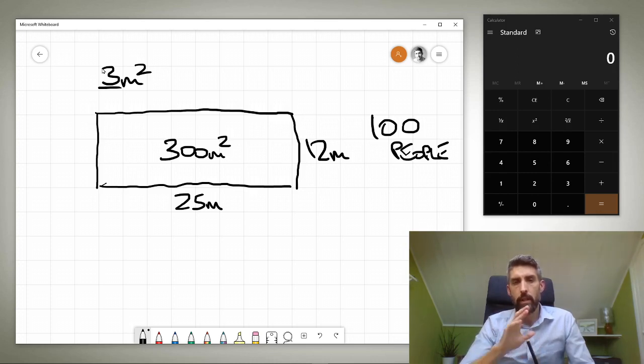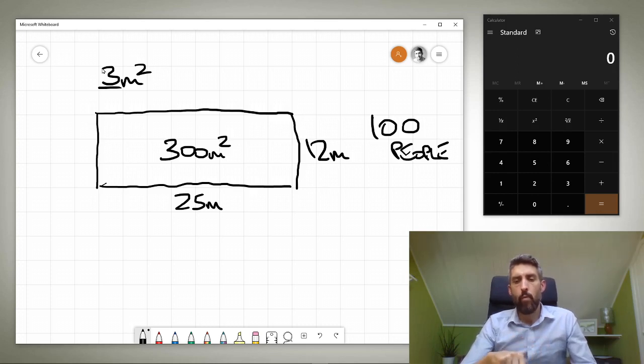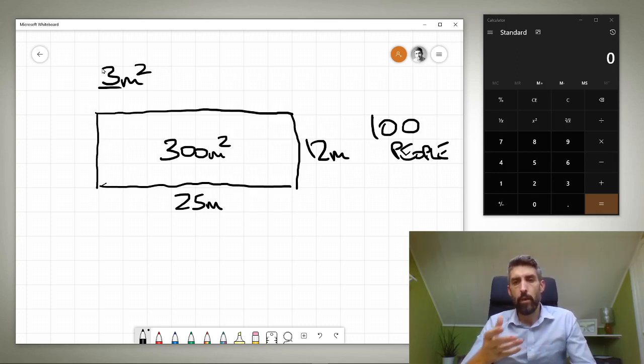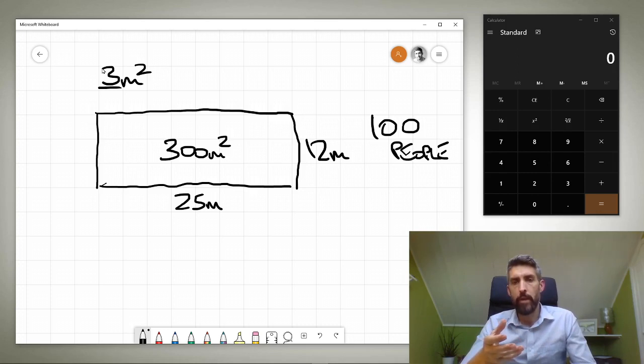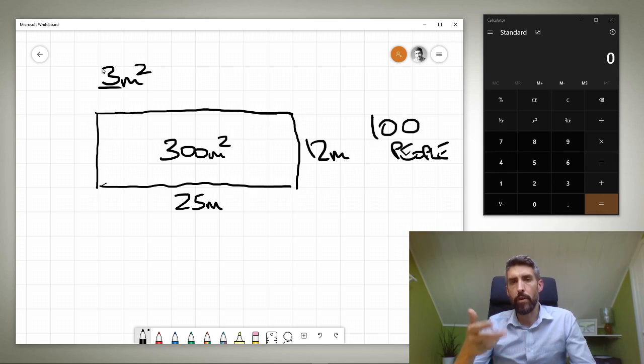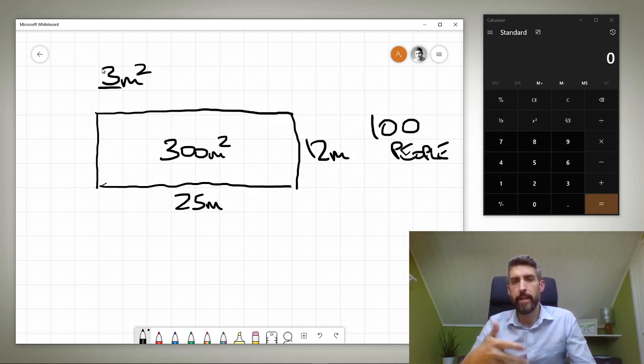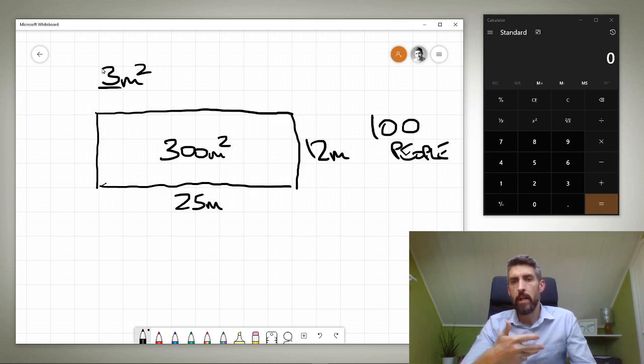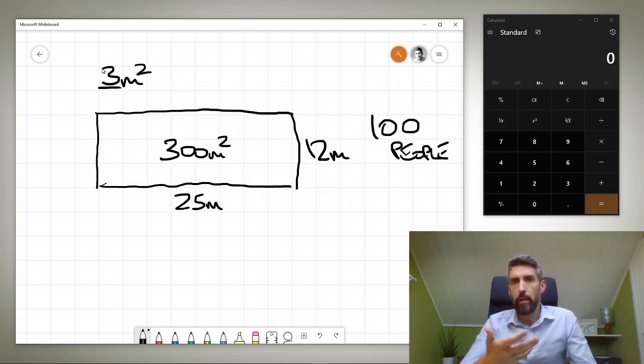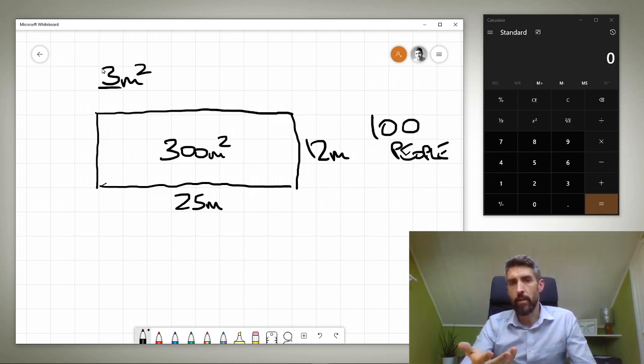So that's the instantaneous bathing load. That's how you work that out. What you also need to work out and record and publish in your normal operating procedures is the daily bathing load, to make sure that you're not overloading the pool day to day, because otherwise you could end up overwhelming the pool plant treatment system and things are going to deteriorate in terms of water quality.